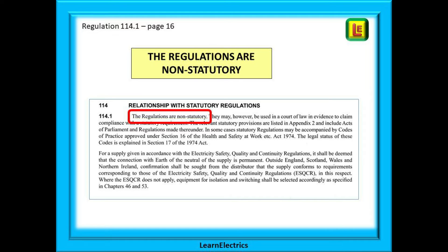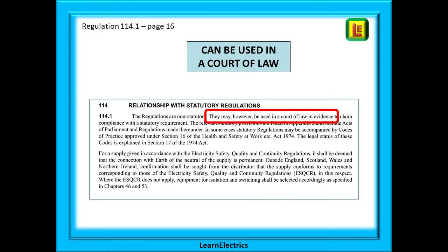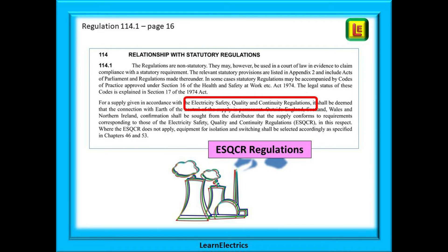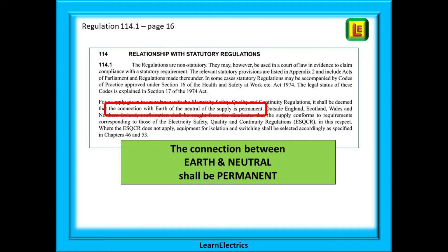Just because it says 'wiring regulations' does not mean they are automatically statutory — they are non-statutory and a code of working practice that we should all abide by. They may, however, be used in a court of law in evidence, because by complying with the non-statutory wiring regulations you will automatically comply with the Electricity at Work Regulations and the Health and Safety at Work Act, which are both enforceable statutory documents. The second paragraph of 114.1 mentions the Electricity Safety Quality and Continuity Regulations, often abbreviated to ESQCR, and also states that the connection with earth and neutral shall be permanent.